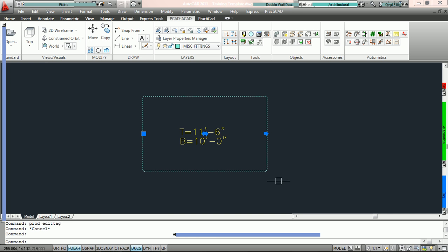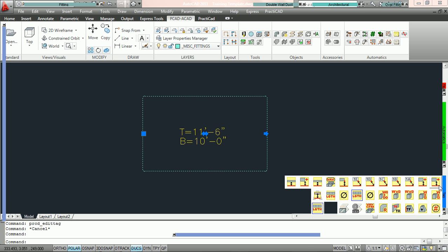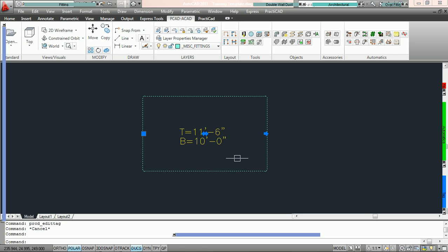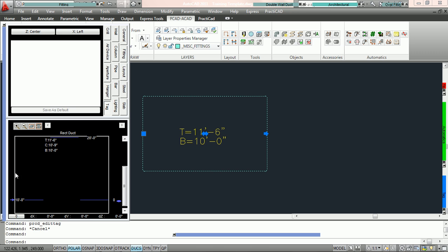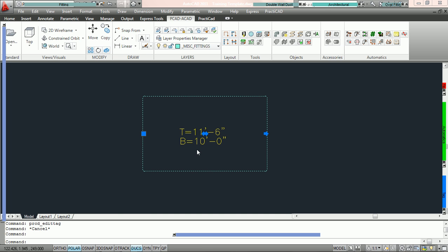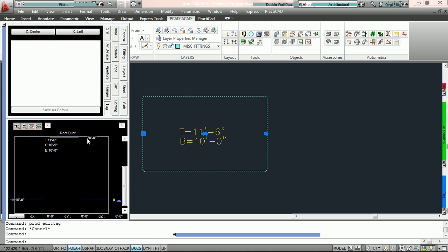So the tags hold the intelligence, and your default data has all of that intelligence, those formulas, already built in. This tutorial is just to explain how they work, because you can create relative marks of any number with any name, and you can use those values to subtract from any elevation tag or any property. In this particular case, we're using it to subtract the bottom elevation and top elevation of the duct from our relative bottom mark, which happens to be elevation mark with name 0.